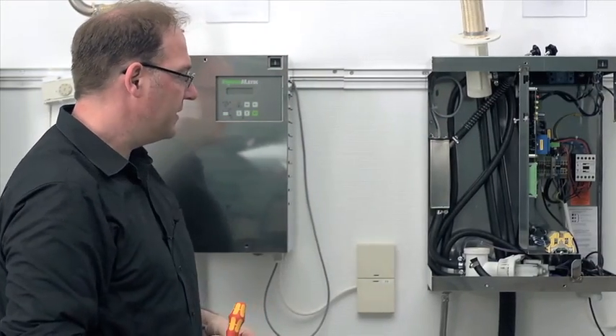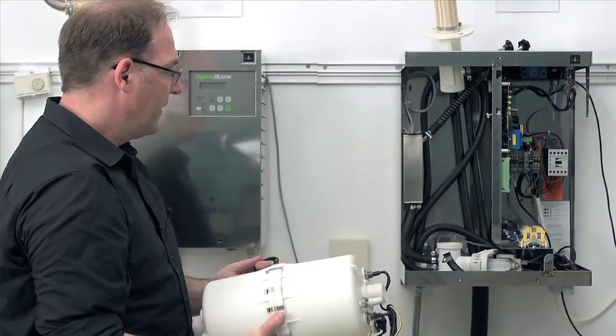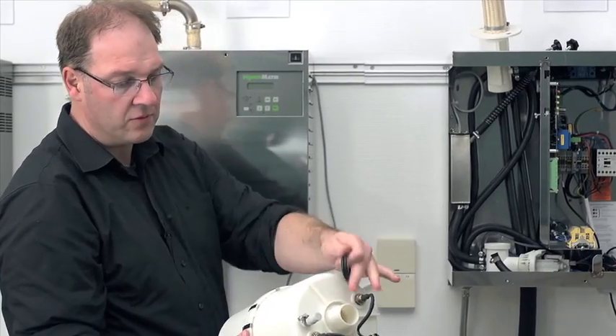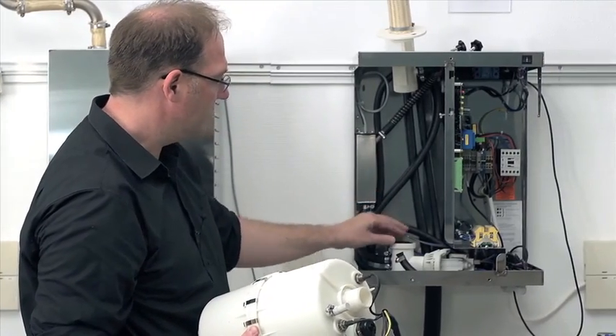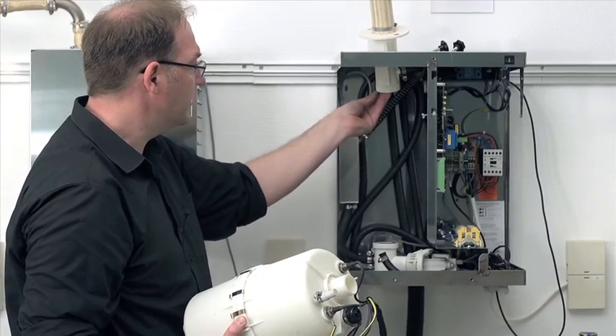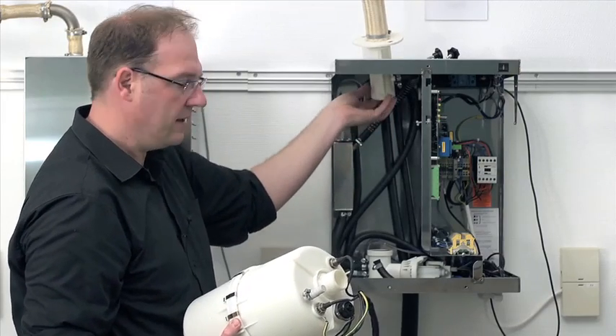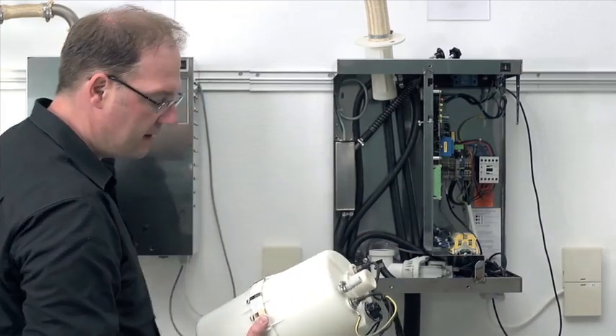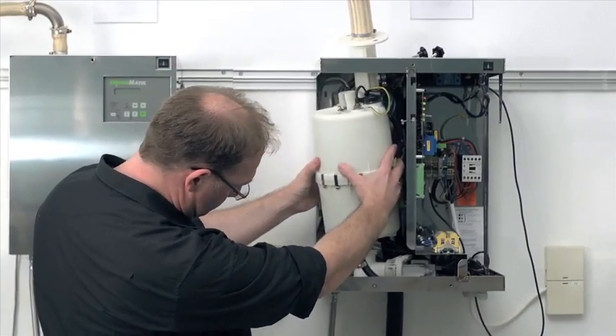Now, after we have mounted the control cylinder, we can go about re-assembling the steam cylinder. We have spoken about the O-ring set earlier, that we want to insert new O-rings in the top and bottom as well. This one is the one for the base, the O-ring, maybe wet it a bit, so it will fit in nicely later on. And at the top here, the second O-ring, insert it into the groove again, wet that a bit as well. And then I could actually place the steam cylinder back into the unit already.